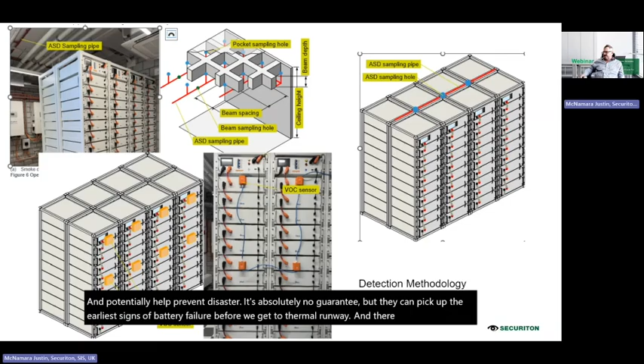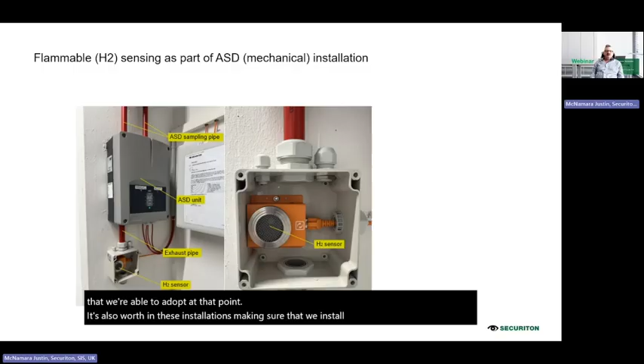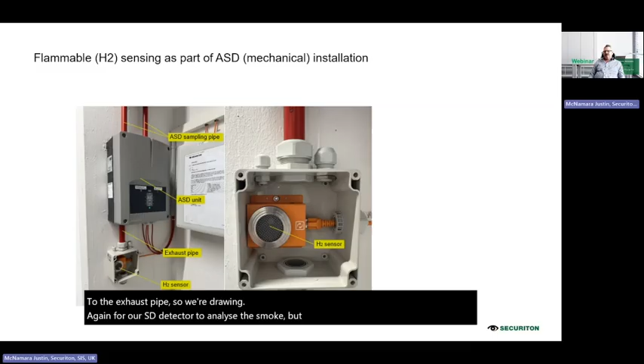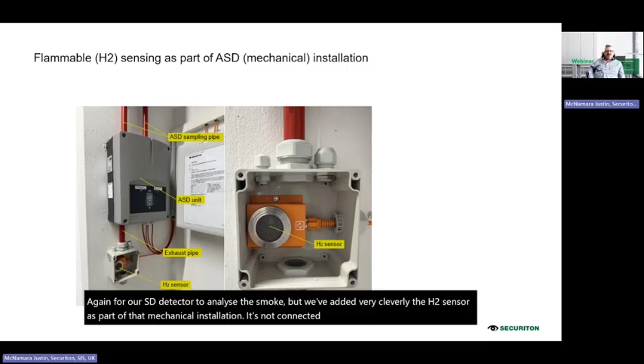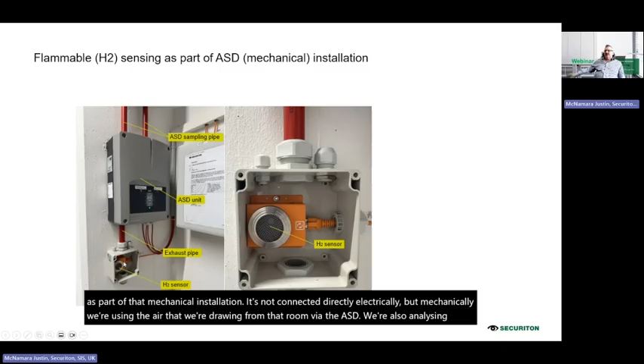It's also worth making sure we install a flammable H2 sensor as part of the installation. This is an actual live picture from our own installation in Switzerland. We have the ASD, as you'd expect, covering the battery storage room, but we've also connected an H2 sensor to the exhaust pipe. So we're drawing in air for our ASD detector to analyze for smoke, and we've cleverly added the H2 sensor as part of that mechanical installation. It's not connected directly electrically, but mechanically we're using the air drawn from that room via the ASD, and we're also analyzing it for H2 - a very neat, clever solution.